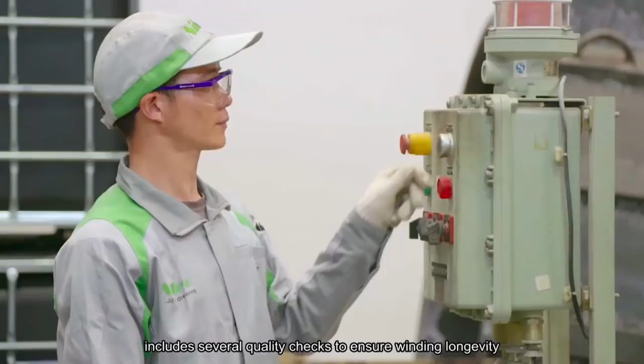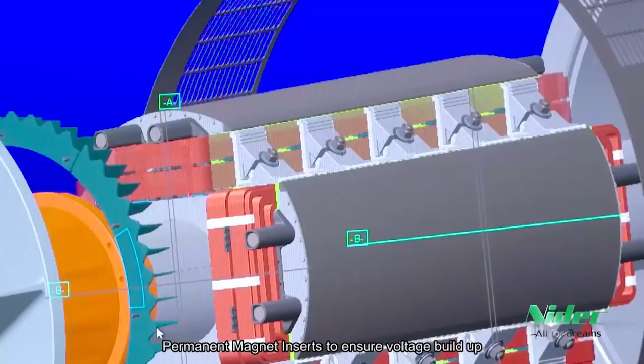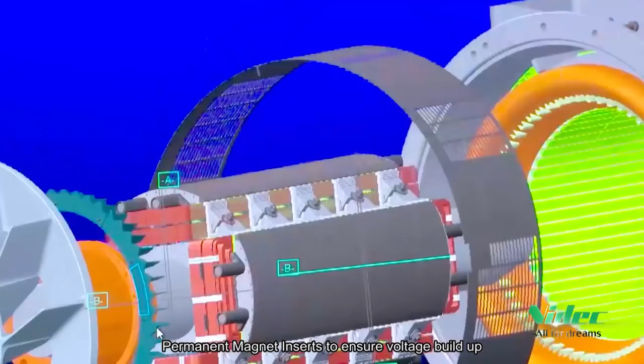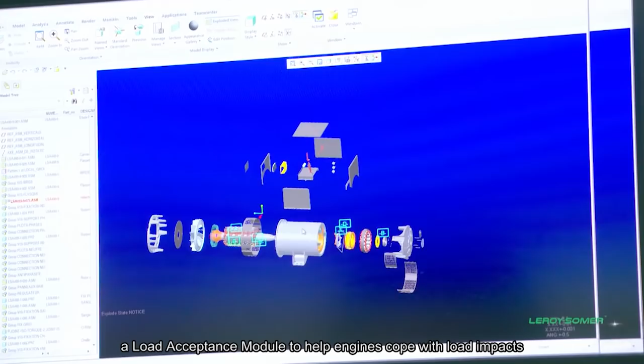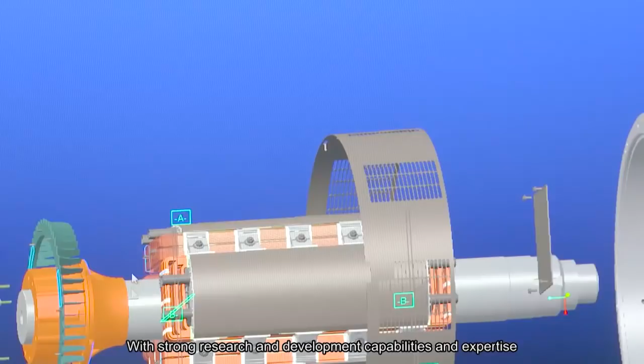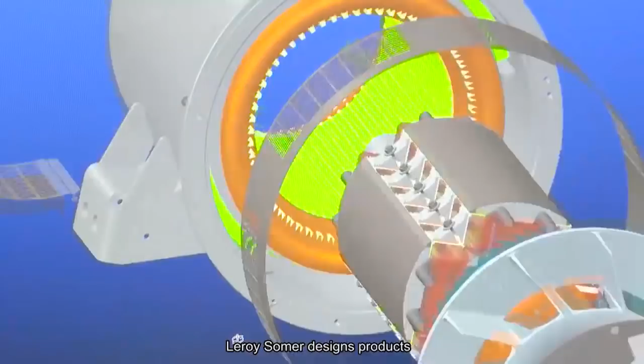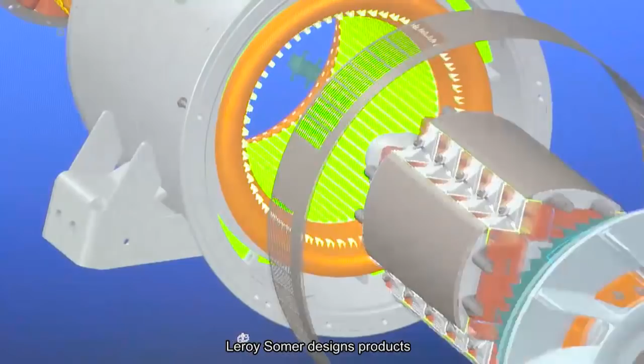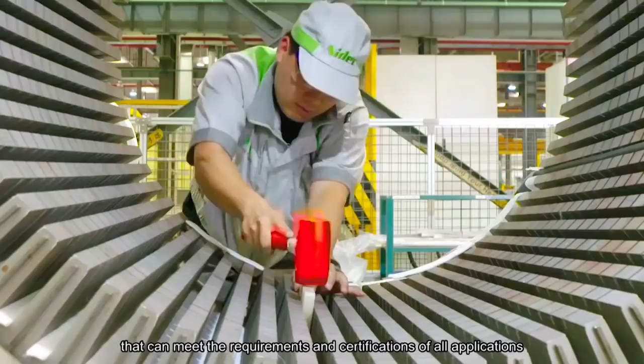Leroy-Somer alternators feature cutting-edge technologies: the patented AREP excitation, auxiliary winding regulation excitation principle, for high short circuit and starting capabilities; permanent magnet inserts to ensure voltage buildup; and a load acceptance module to help engines cope with load impacts. With strong research and development capabilities and expertise, Leroy-Somer designs products that can meet the requirements and certifications of all applications.